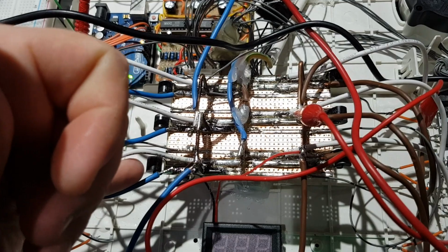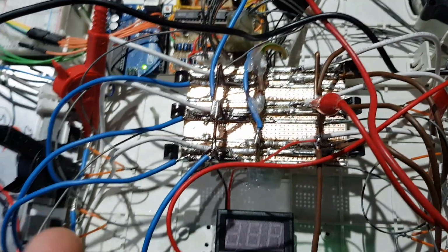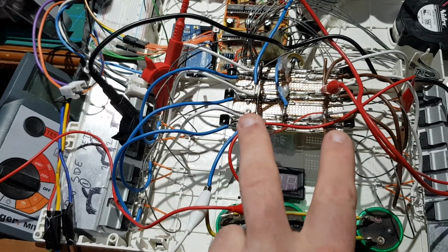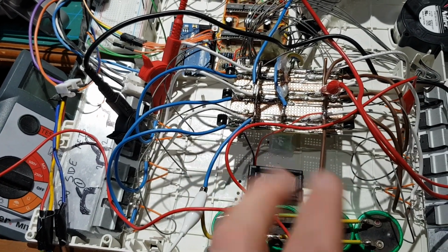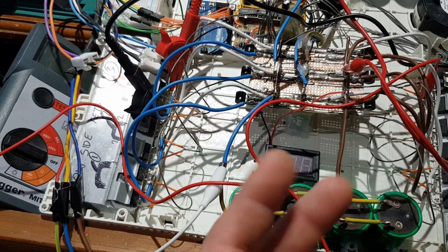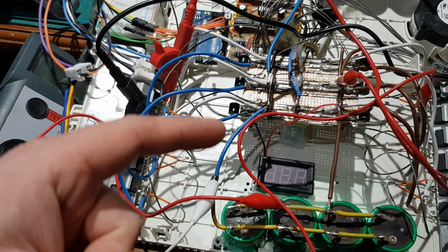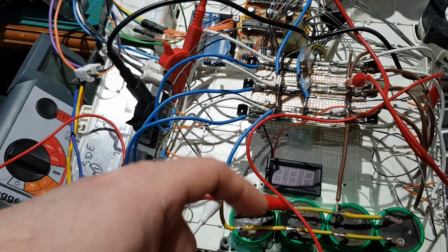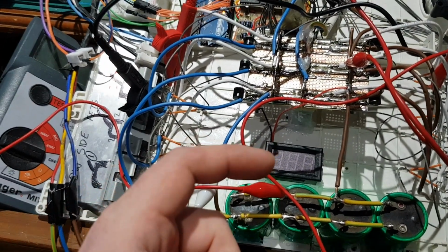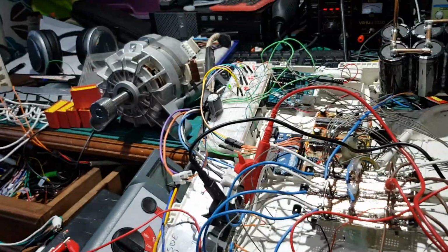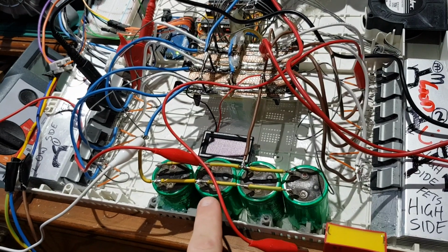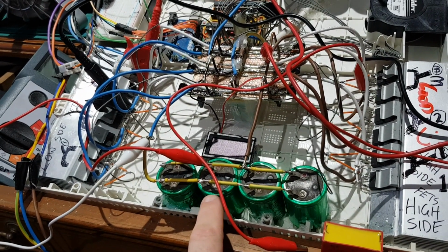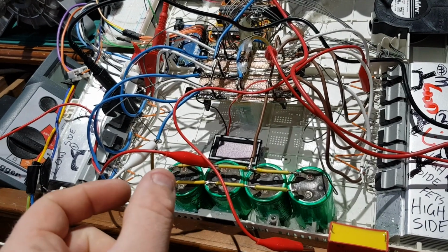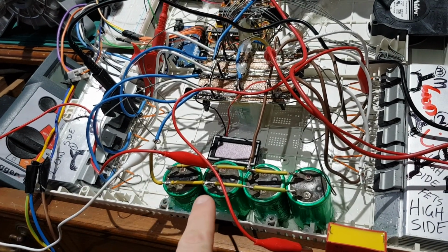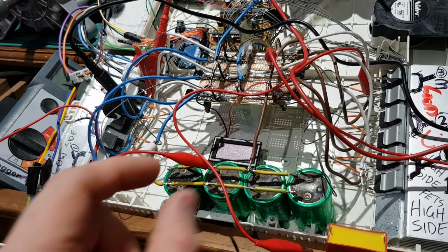Because this setup here takes the energy and essentially pumps it back into the DC bus. If you imagine, the higher the DC bus gets, the energy has to rise to that point before it can get absorbed by the DC bus. Let's say for example you've got 200 volts across these caps and you try to charge them to 210 volts. Let's say you're increasing your voltage. These aren't going to draw any current until you reach above 200 volts, and then these will start to charge up. So that's what you're seeing there.